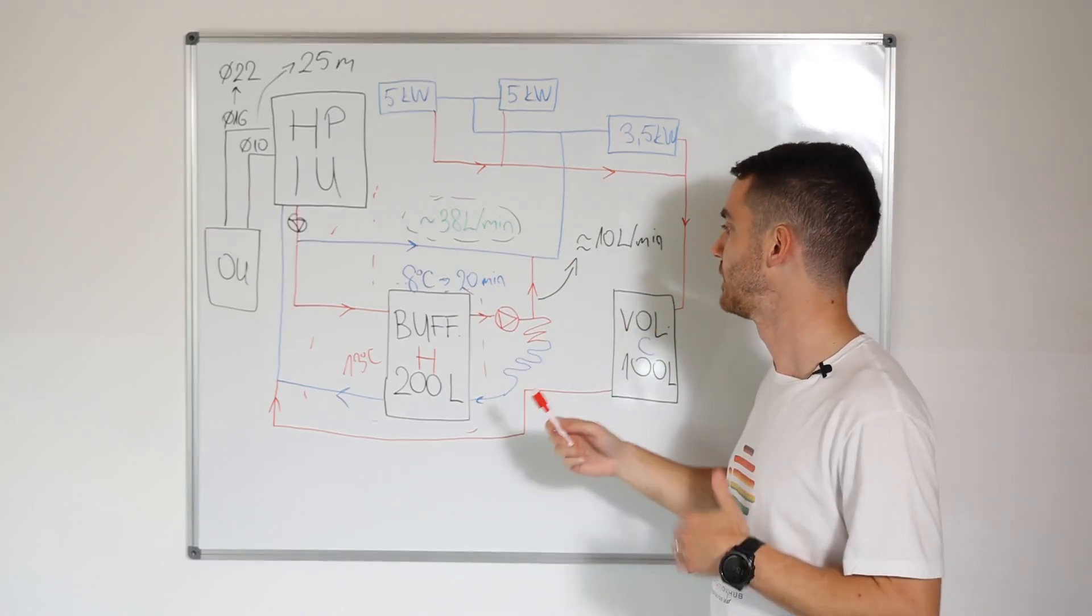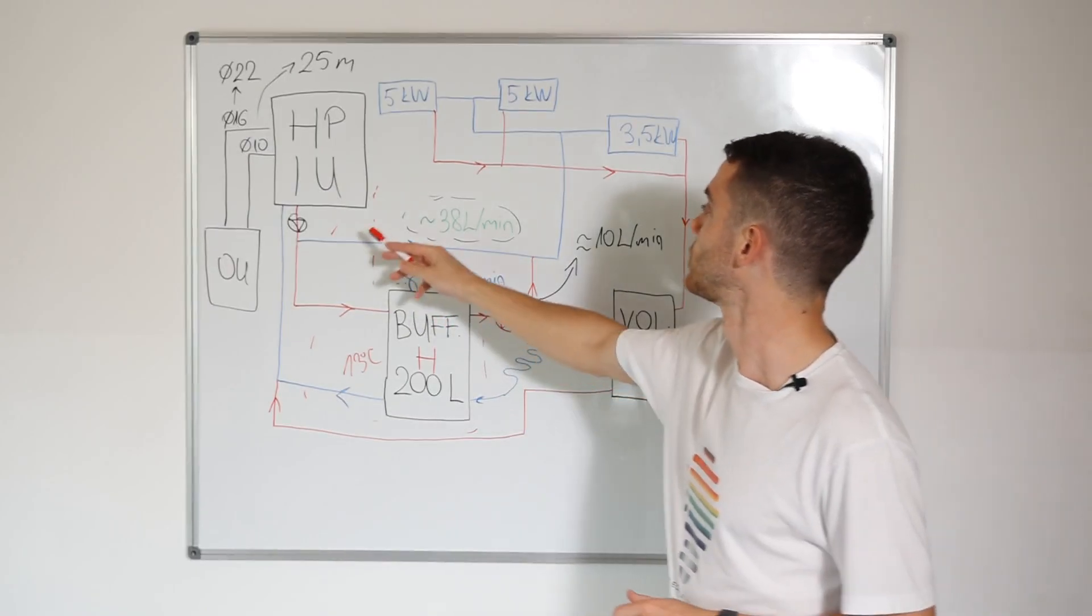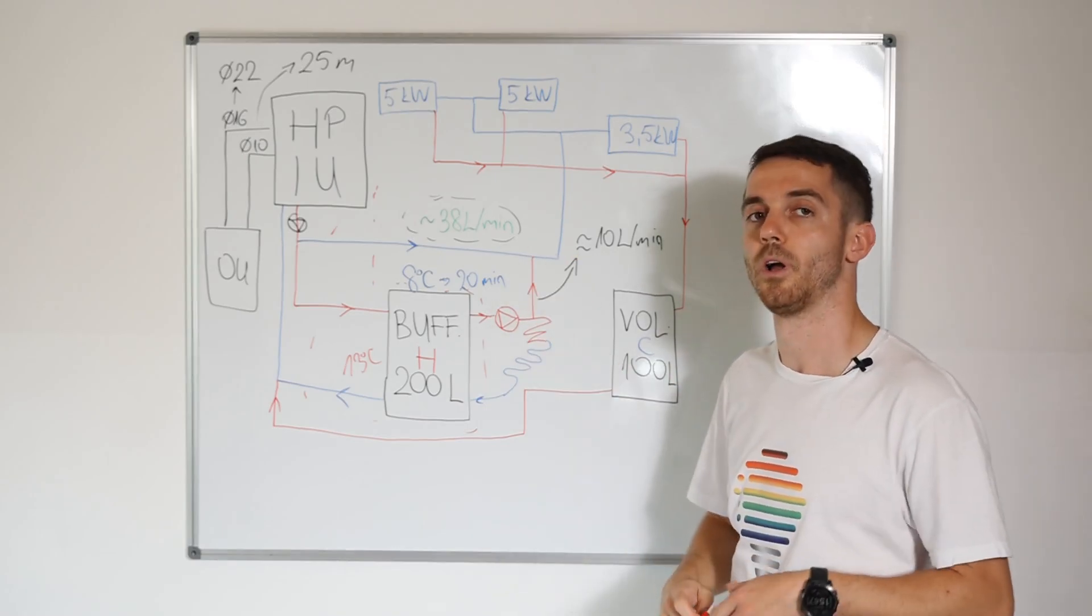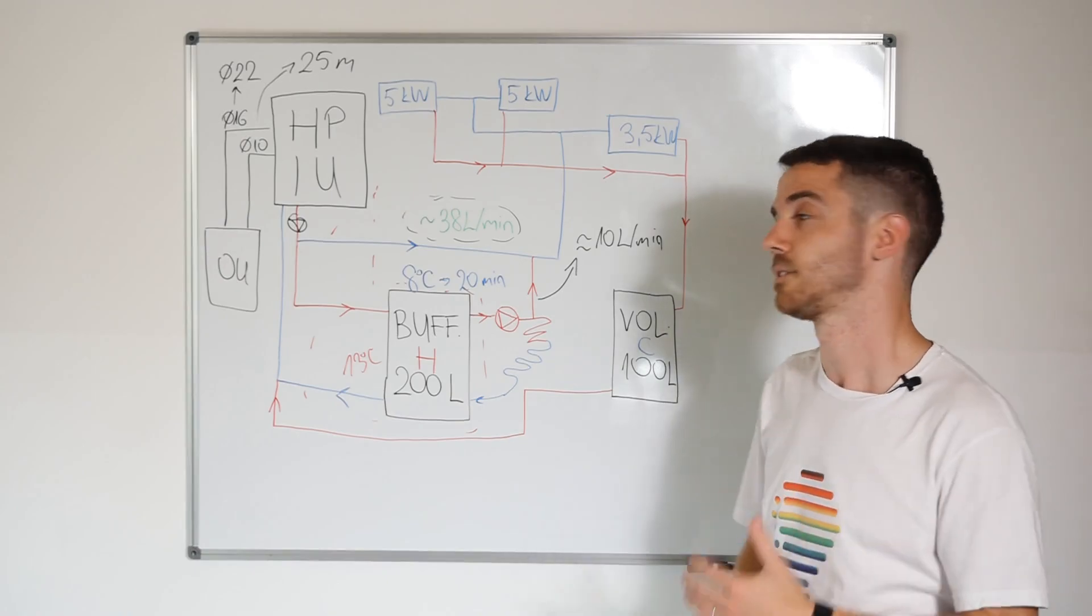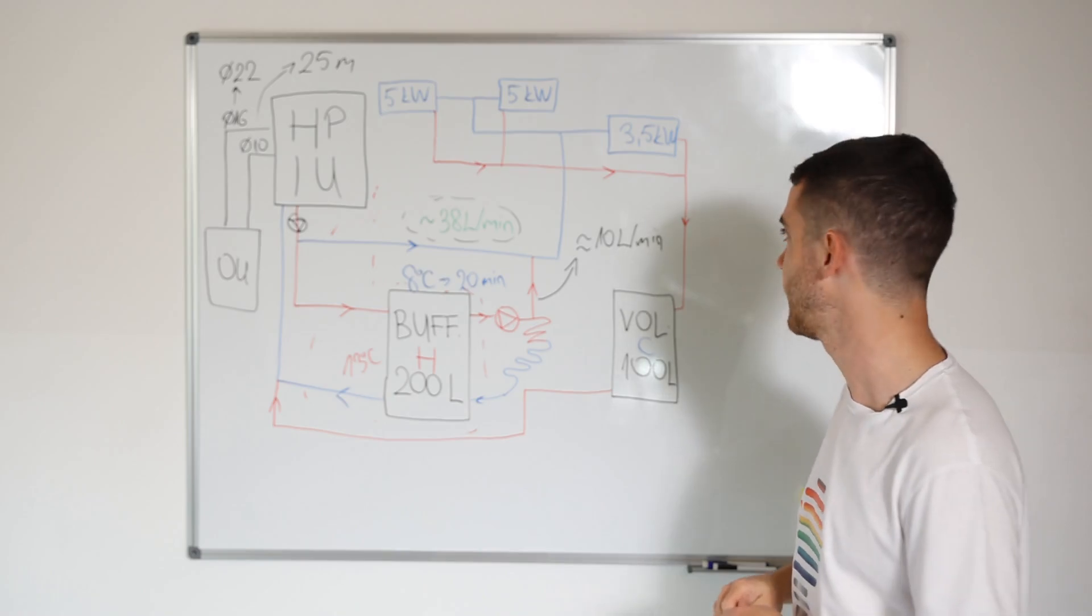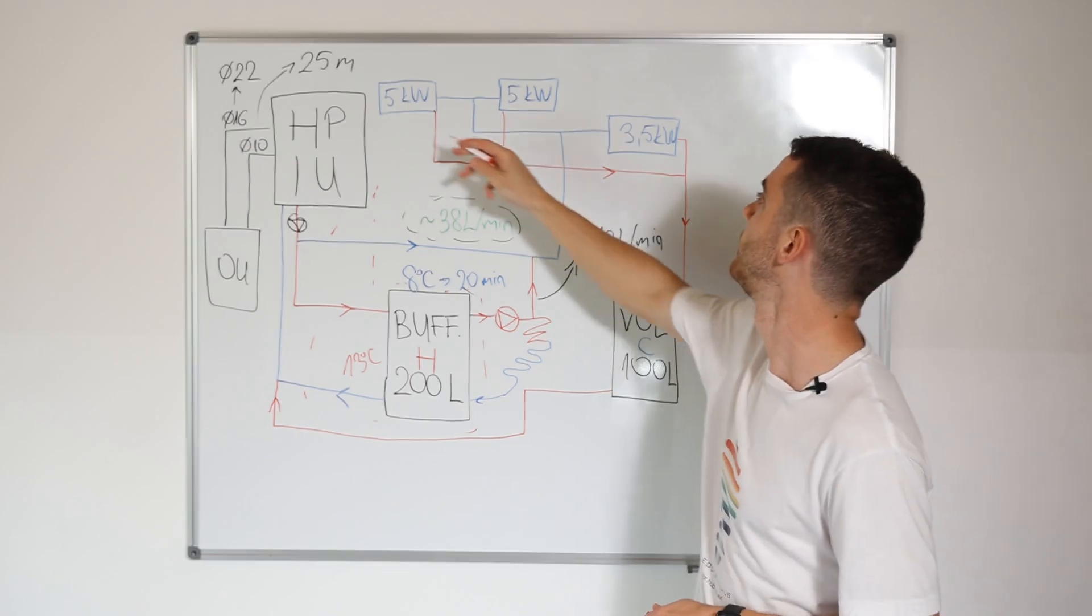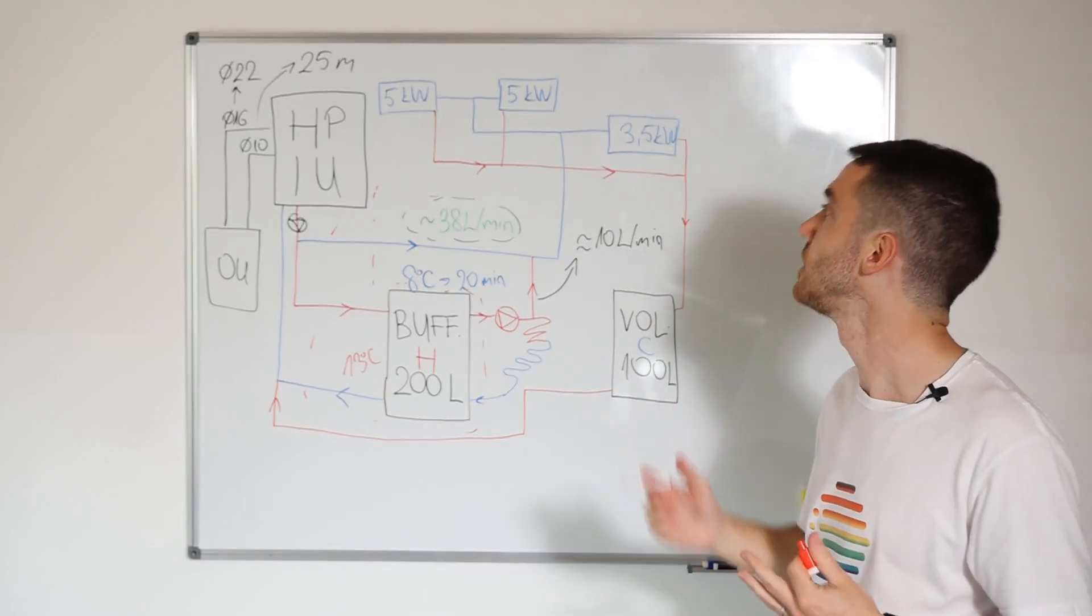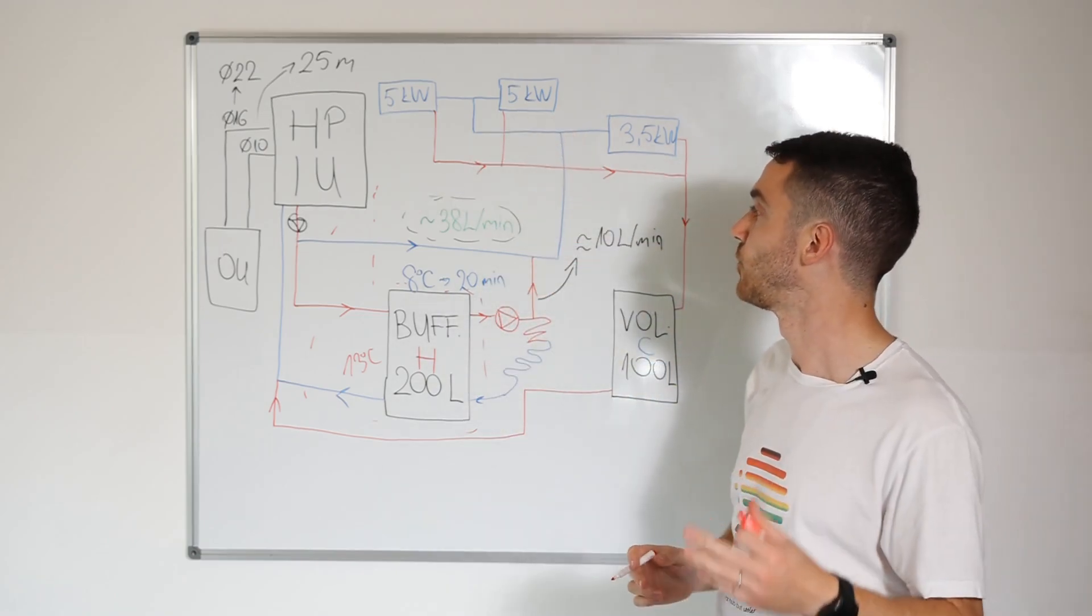This is, someone will say in cooling, you must always ensure this. This is also not the problem if you have enough volume, enough pressure drop, and if you don't have motor valves which will close the fan coils or radiators. And what is also missing here, even if you have such kind of regulation, so installer and designer, they thought there are no valves. So we have always enough flow rate, but it's always good to put something like this.